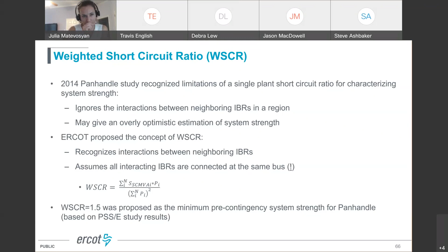So we reevaluated the Panhandle area in both phasor domain stability studies, so PSS/E type of studies, as well as detailed electromagnetic transient studies, EMT studies that we do in PSCAD, in 2016, 18, and 19, and now onward every year, basically. And a weighted short circuit ratio of 1.5 was still found appropriate. So basically what we do is actual study, but then we see if this high-level indicator of 1.5 short circuit ratio is still indicative of system strength above this level.